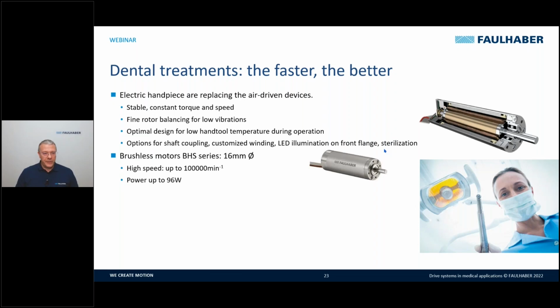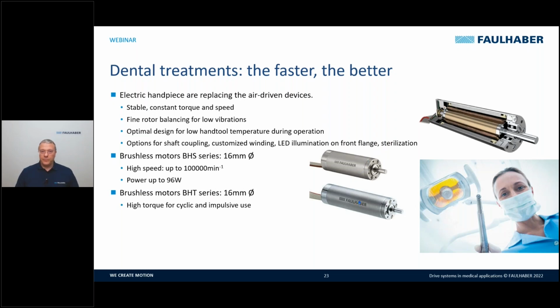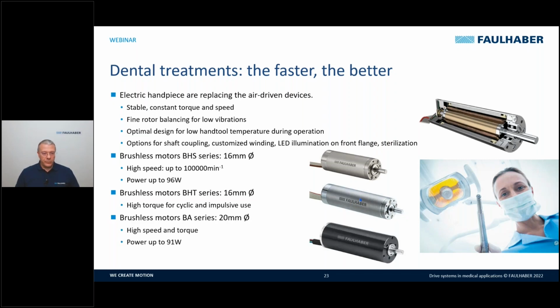For this reason, we have a brushless motor, 16 millimeter and with a high speed up to 100,000 RPM, or for high torque operation, depending on the type of operation that we have to do with the hand tool. Brushless motor with 20 millimeter diameter like this, small motor, power up to 91 watt in this case. We can reach almost 100 watt. This is in comparison with the air-driven device, a factor of 2 or 3 on the power range.